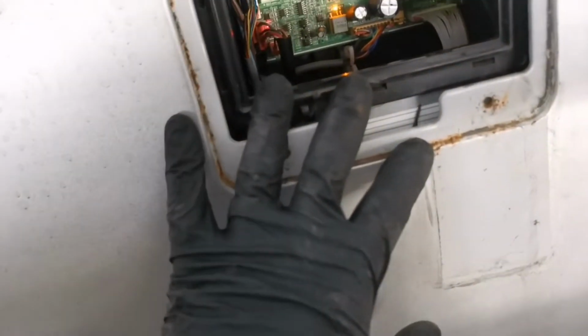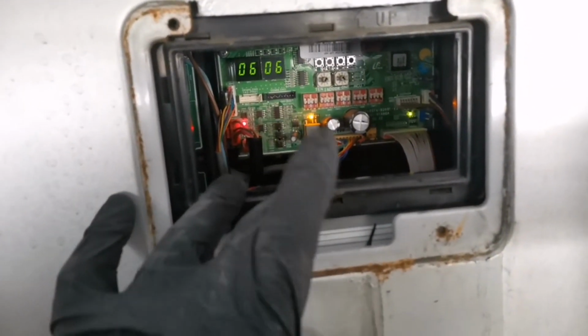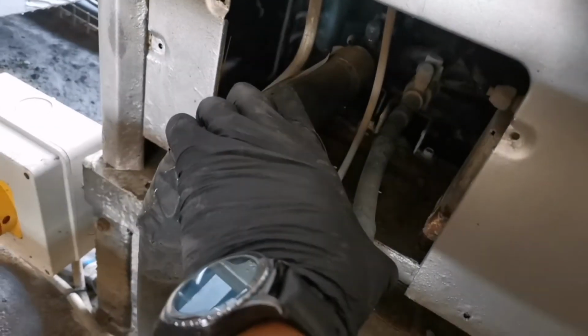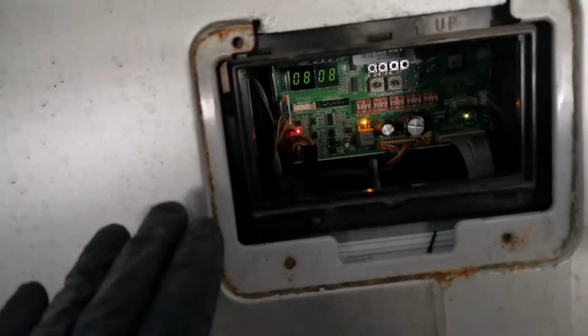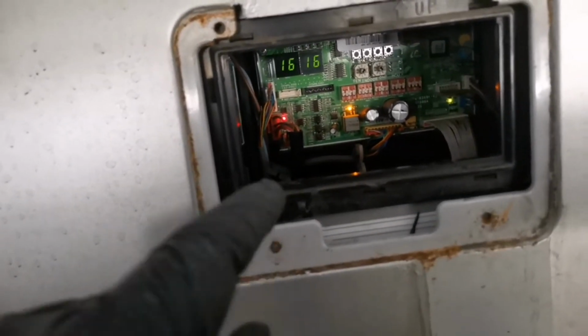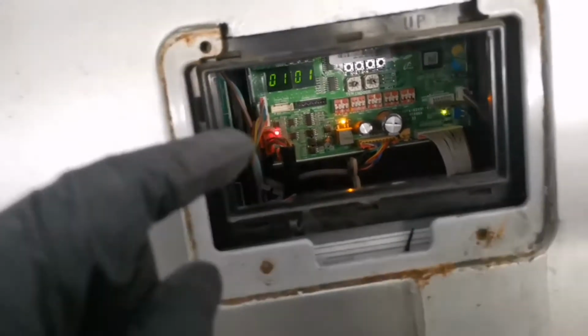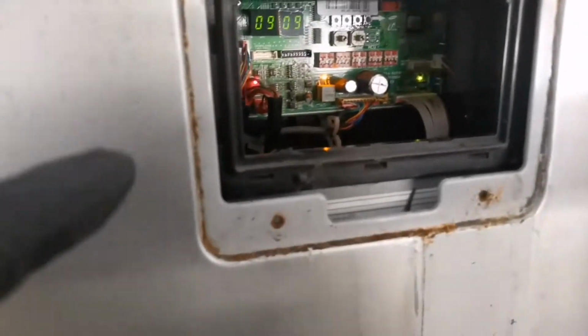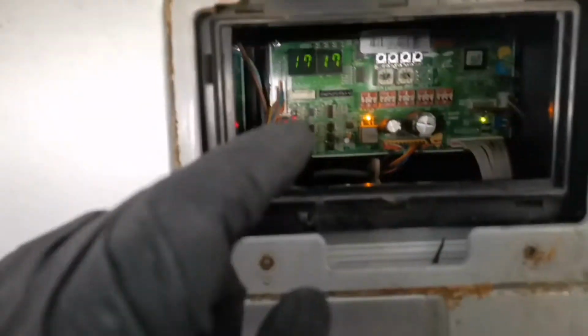So right now I've checked out this system. This system has got a 152 error code. This is a heat pump. This is a heat pump and not a heat recovery. So the possibility of cross operation has to be scratched out. So this unit over here has got a defective indoor expansion valve coil that we have to replace on unit address 5. So I've made my notes as I go along.